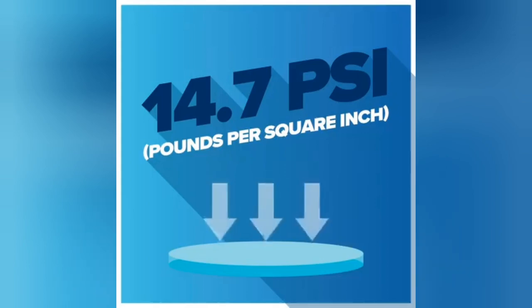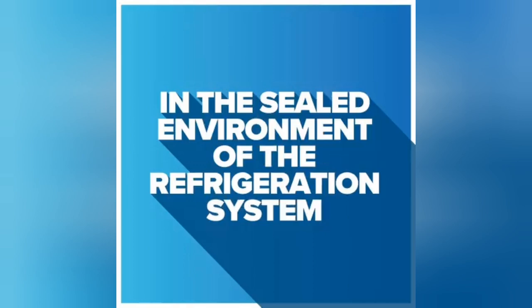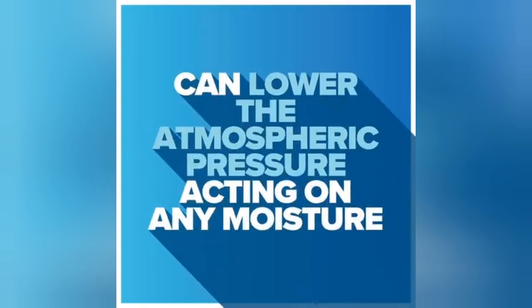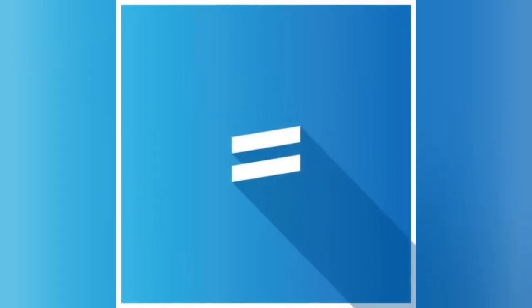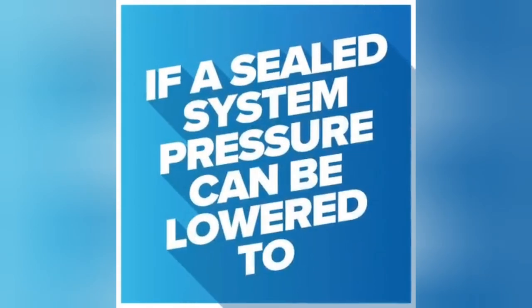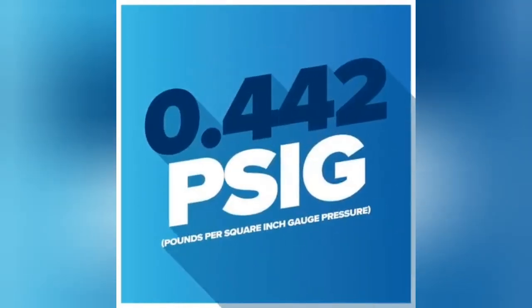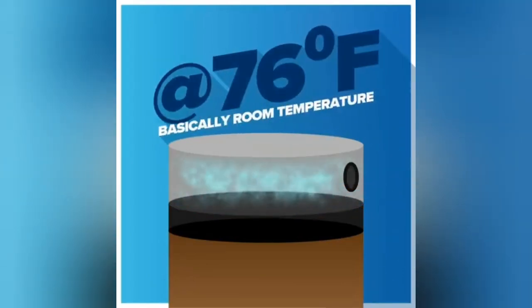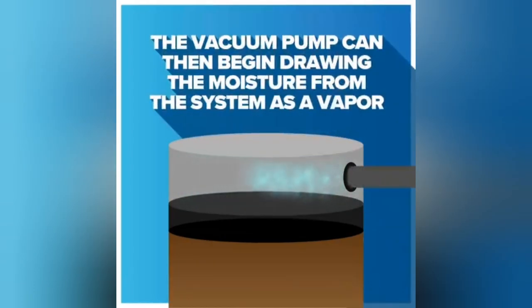In the sealed environment of a refrigeration system, a vacuum pump designed for this purpose can lower the atmospheric pressure acting on any moisture present in the system. The lower pressure will also mean a lower boiling temperature of that liquid. For example, if a sealed system pressure can be lowered to 0.442 psia — that's pounds per square inch absolute pressure — the moisture will boil and change state from a liquid to a vapor at 76 degrees Fahrenheit, which is basically room temperature. The vacuum pump can then begin drawing the moisture from the system as a vapor.